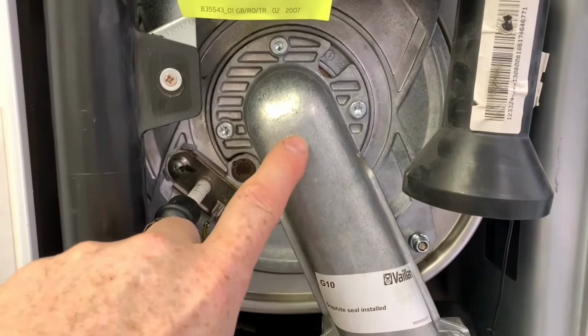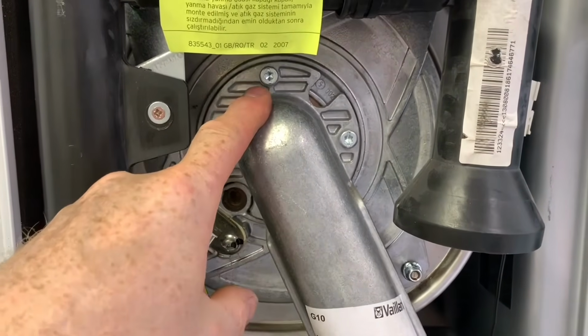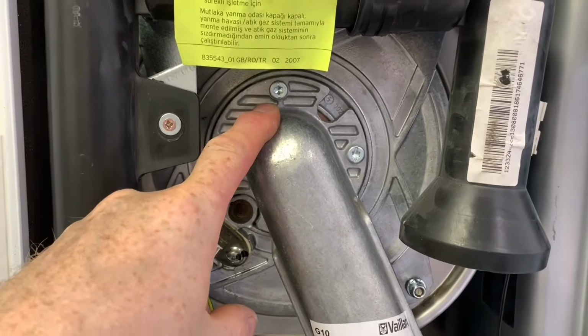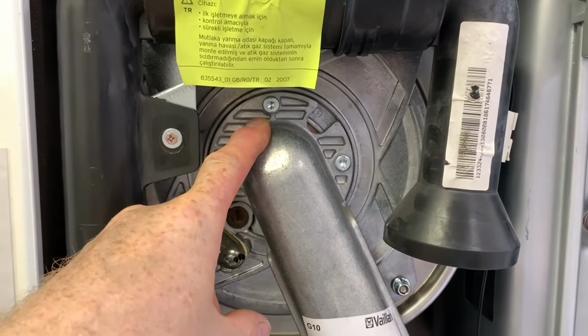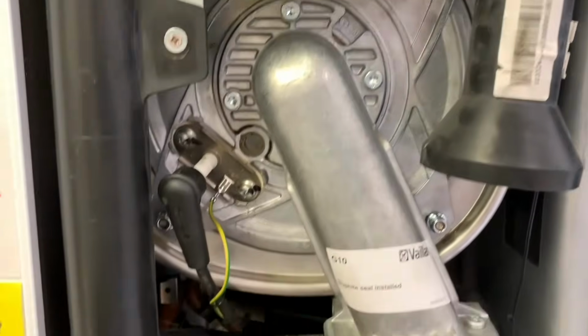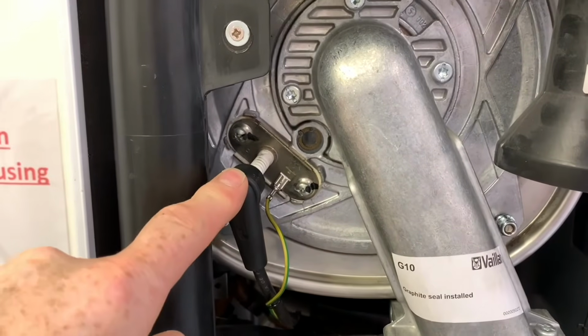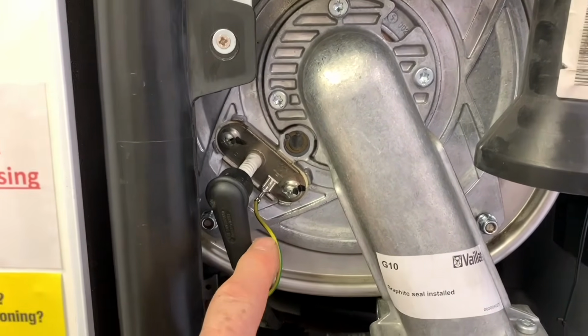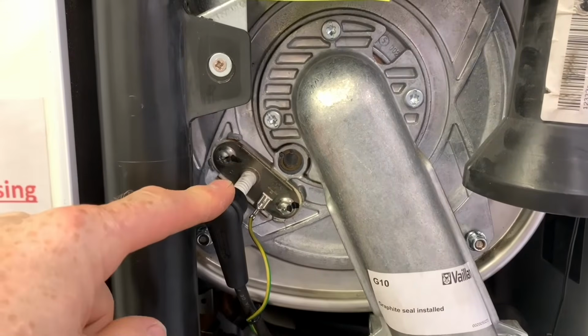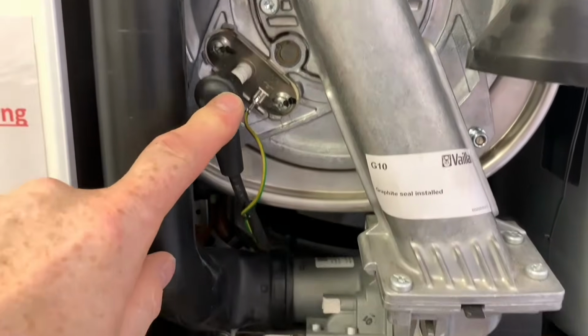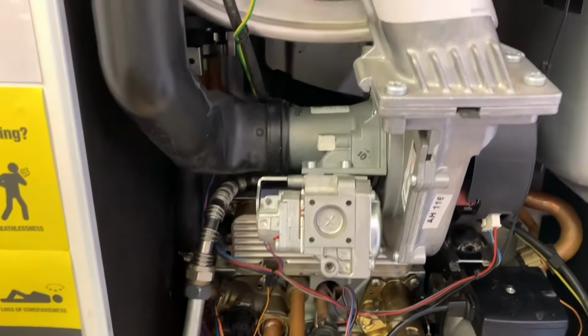Now behind the silencer, this is the burner. This is the burner door. This is a G10, however you say that. Then this is our spark electrode HT lead with that earth wire. This does flame rectification as well as ignition, and that will go back down to the board.